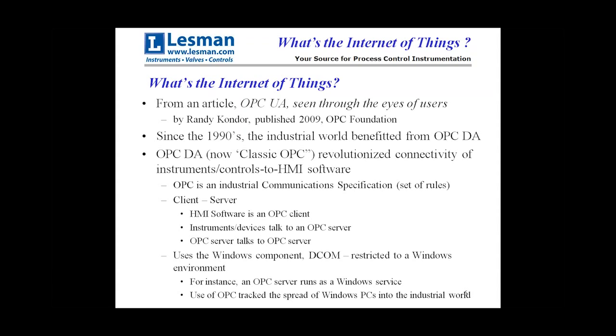In reality, OPC DA is just a specification — a set of rules that tells how the data is going to be communicated back and forth. It's a client-server architecture: HMI software is the OPC client, out in the field you've got field devices, and an OPC server talks to those things and then talks back to the OPC client. The thing is, it uses a Windows component called DCOM, which restricts it solely to a Windows environment. OPC servers always run as a Windows service.